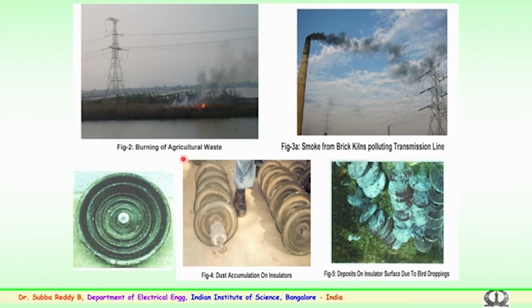This shows the artificial or man-made problems for insulator strings, which could fail much before their life. The reason may be the burning of agricultural waste in particular areas, such as sugarcane. After the crop is completed, they burn the remains, which causes a lot of dust and contaminants that settle on the insulator surface over a period of time and become hardened on the surface, and during monsoon conditions the surface becomes wet and likely to flash over.